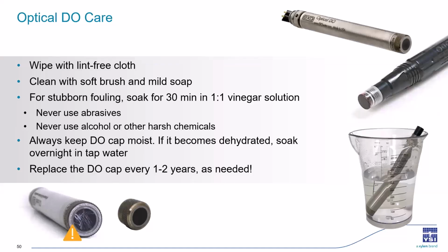Always keep the optical DO cap wet. If it dries out, you can try to rehydrate it by putting it in tap water overnight. The DO cap generally has a life of about 1 to 2 years, but may last even longer with proper storage and care. So go ahead and make sure you're paying attention to your data and your calibrations. If you are having trouble calibrating, that may be a sign that you have to replace that cap. So just go ahead and replace the cap on it.